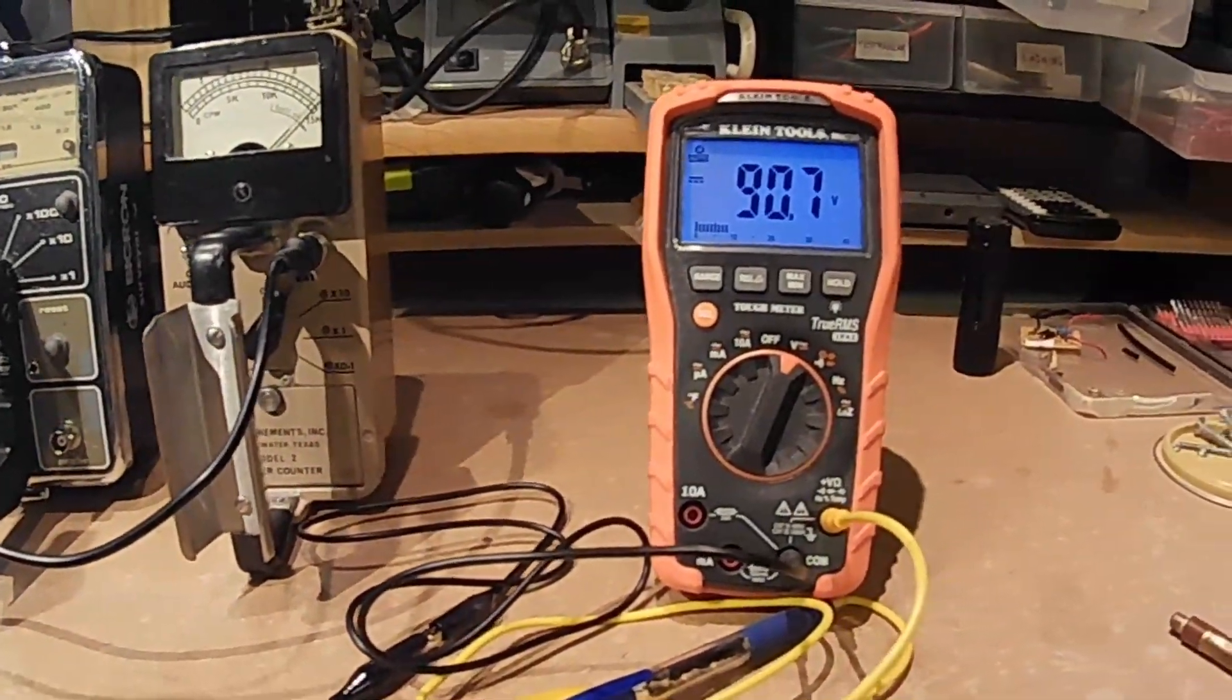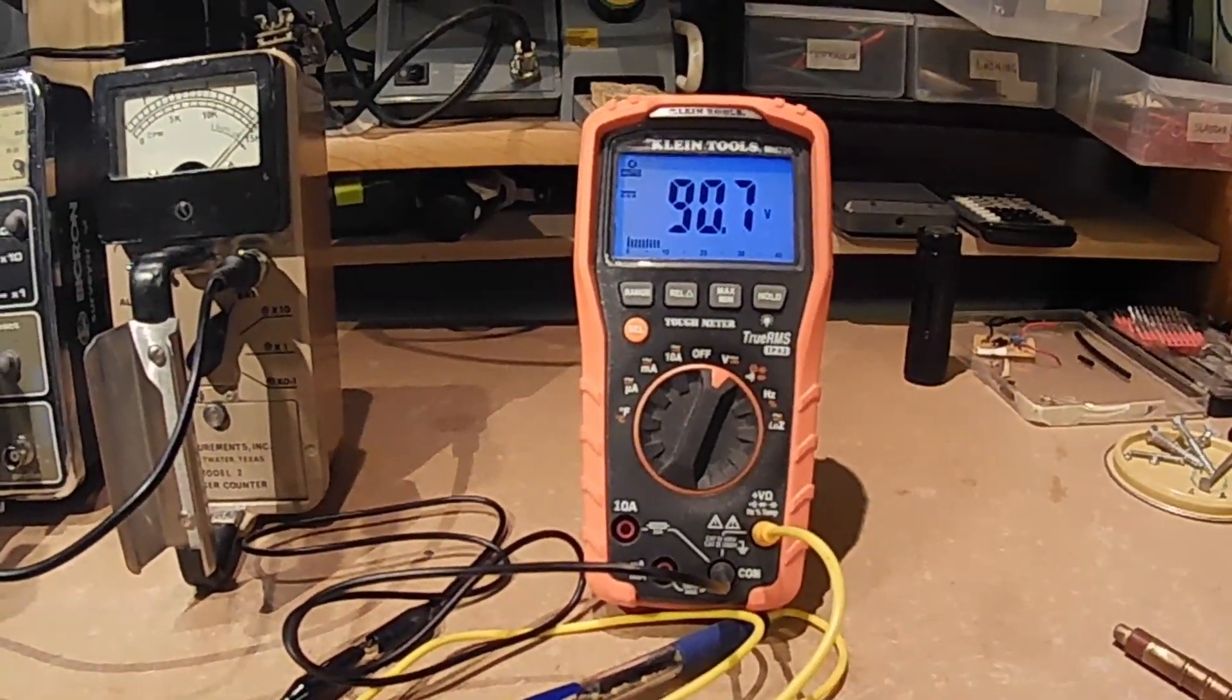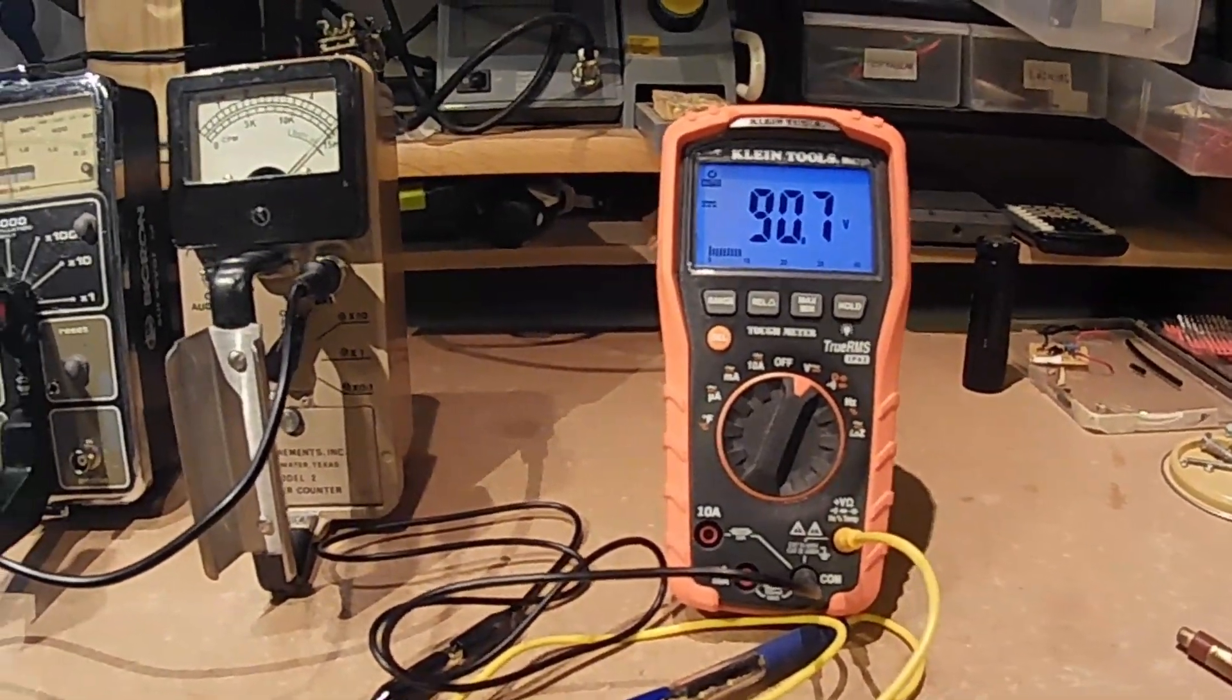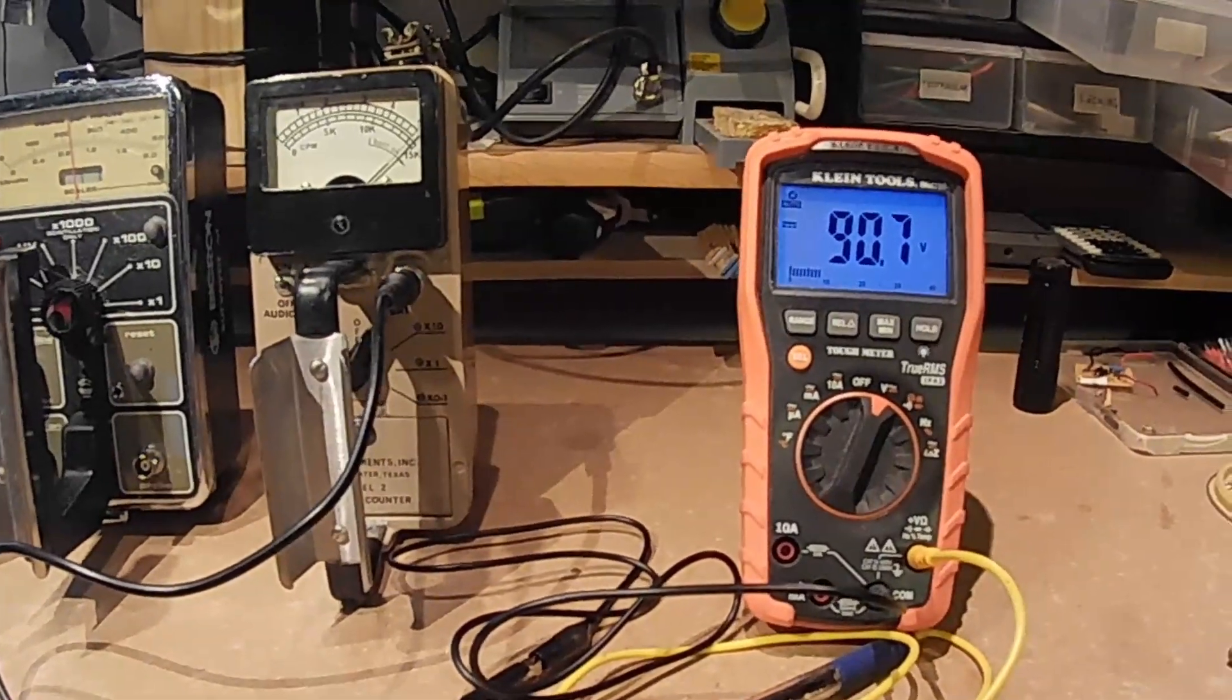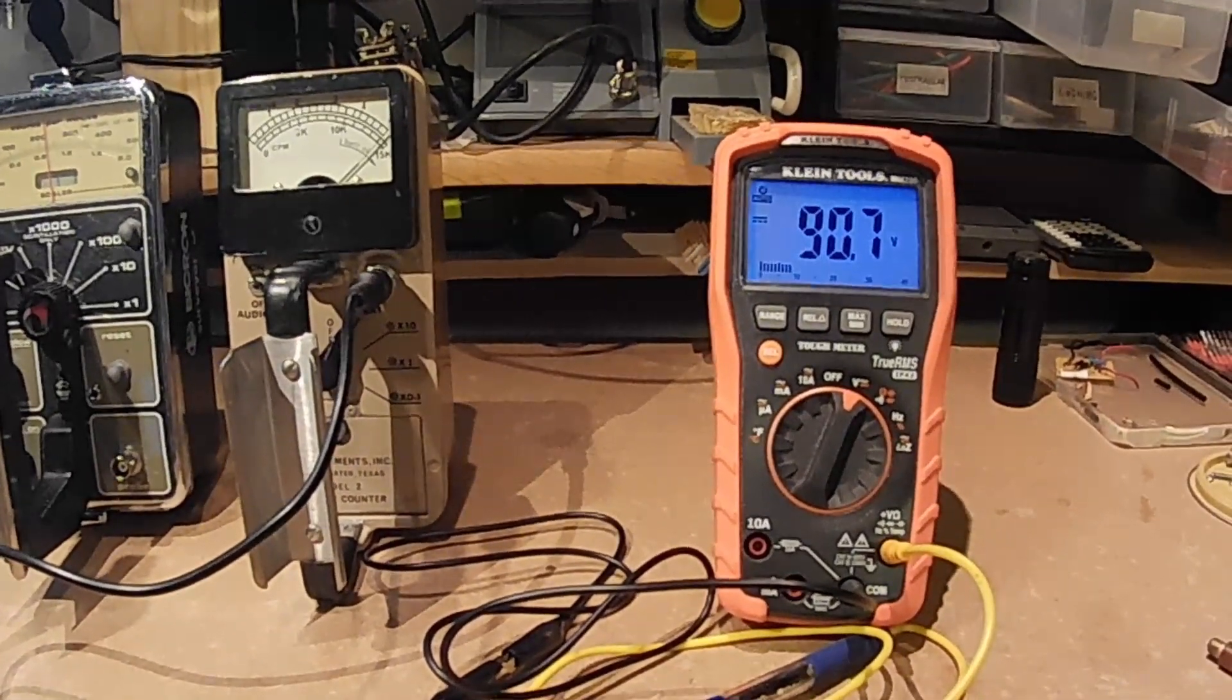Many rate meters are set to 900 volts as standard. At this voltage, most scintillation detectors and some Geiger tubes work well.